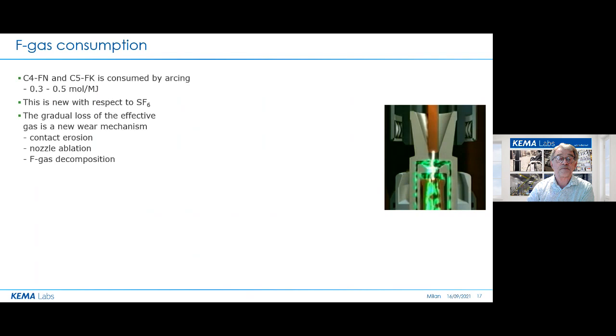existing one. Well, here you see again the arcing chamber of a gas breaker. So due to the intense heat of the arc, there is a loss of mass of the arcing contact here, and there is also a so-called ablation, a loss of matter of the nozzle. Well, the new wear mechanism is decomposition of F-gas.